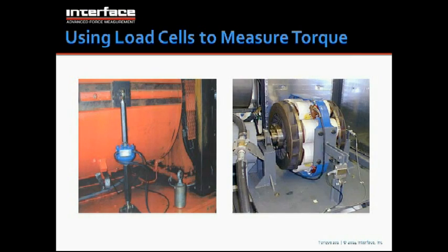Another way to measure torque, and we try to talk about this with customers as much as possible, is, if you really want to measure torque, you might be able to do it using a load cell, and that's the least costly approach in many cases. These are two examples of eddy current dynamometers where a load cell is used to actually hold the housing of the dynamometer, and it's at a set distance from the center line of rotation, and so as the shaft inside spins, basically the housing wants to follow along, and you keep it from doing that with a load cell, and you can measure torque that way, and that works quite well.